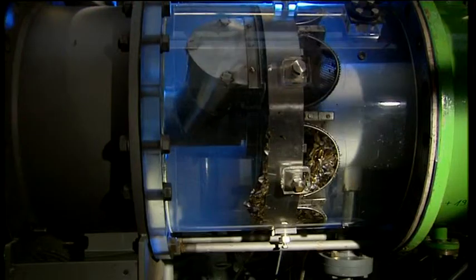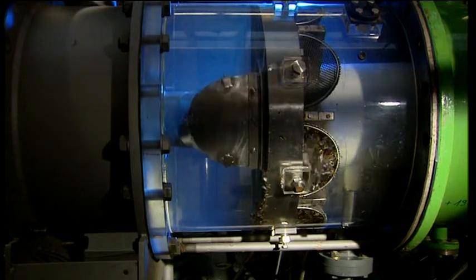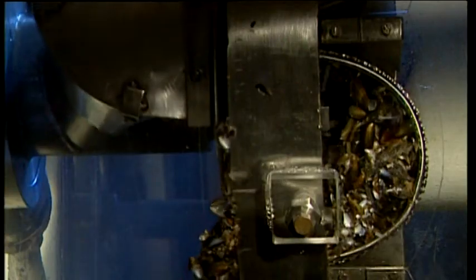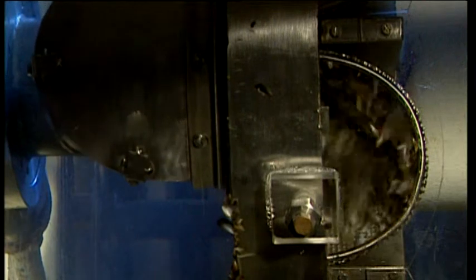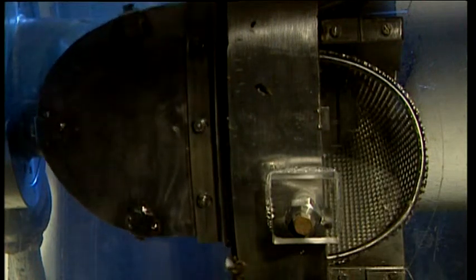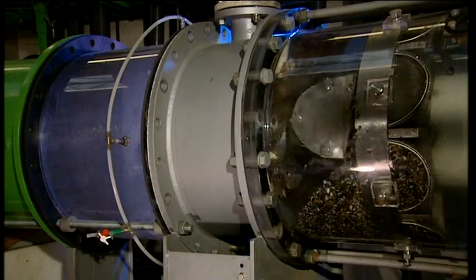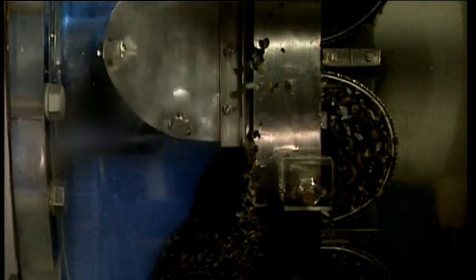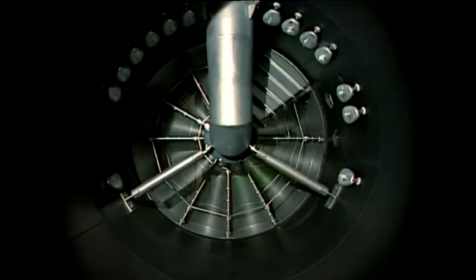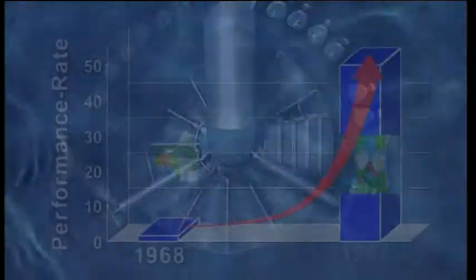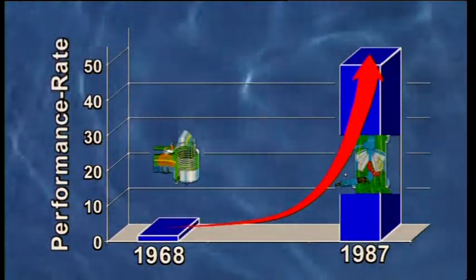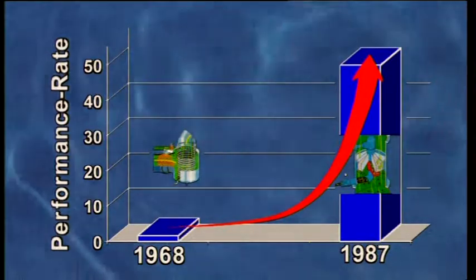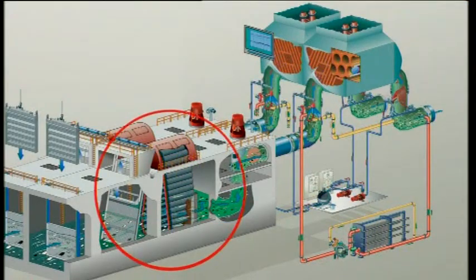Instead of storing macrofouling, as was the case with the earlier voluminous mussel filters with their large surfaces, high-performance filters efficiently flush all coarse impurities out of the cooling water system as quickly as possible. This reduces pressure loss in the whole system, allowing the pump to produce a higher capacity. Taprogge high-performance filters are more than 18 times more efficient than mussel filters. The fact that the travelling band screens are no longer necessary means that construction work in the cooling water extraction area can be significantly reduced.